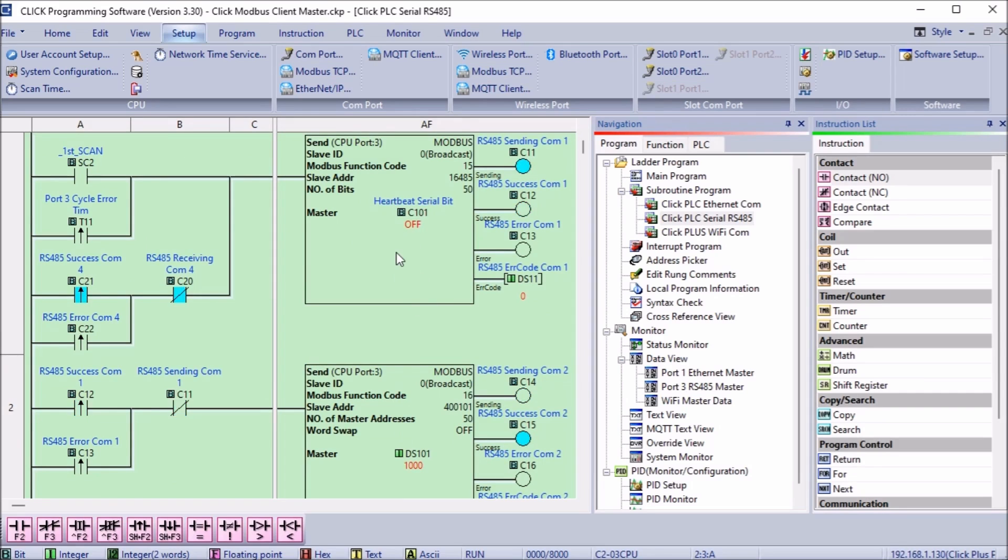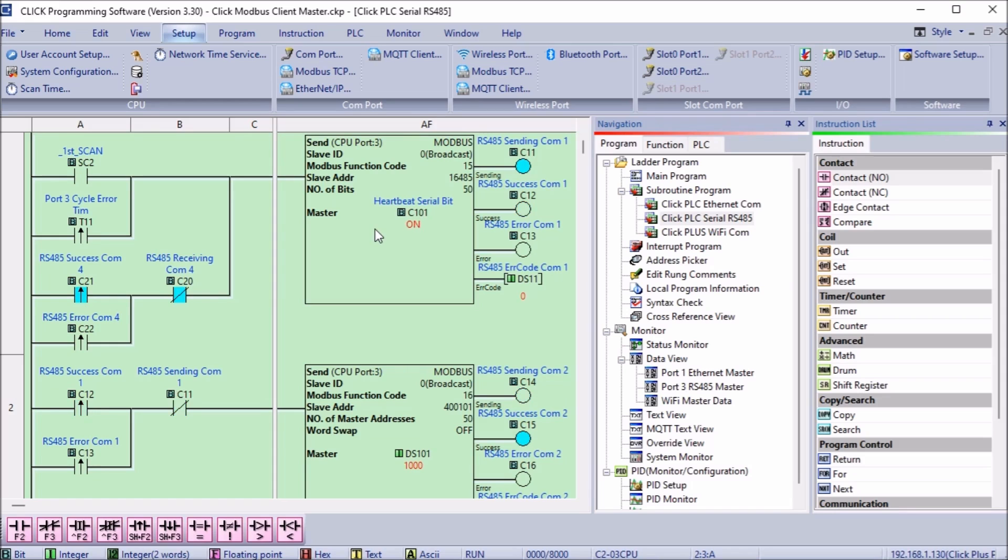The first two lines of the controller will use the send instructions to write information into the slave unit. You will see that the slave ID is set to zero. This unique mode will broadcast the message to all Modbus RTU slaves on the network. Since we only have one slave, we could have also used the value of one.